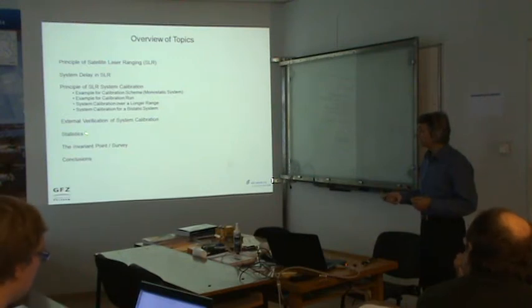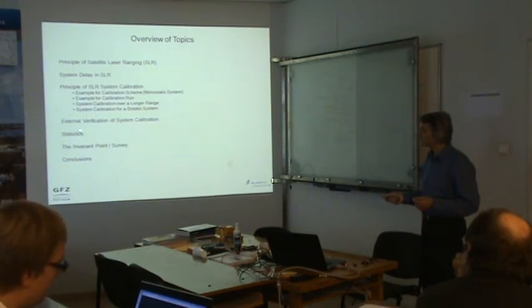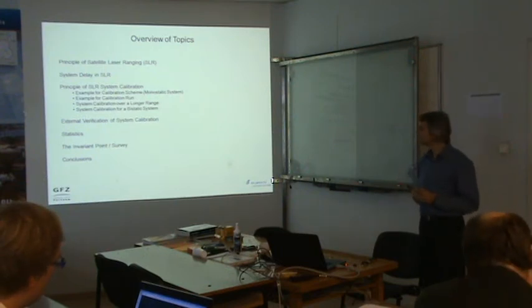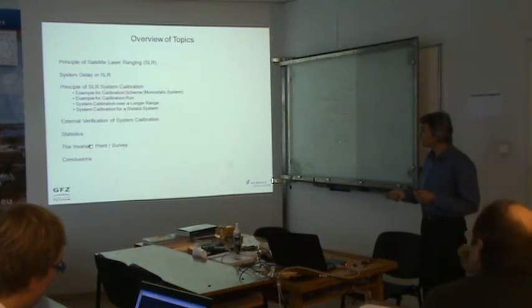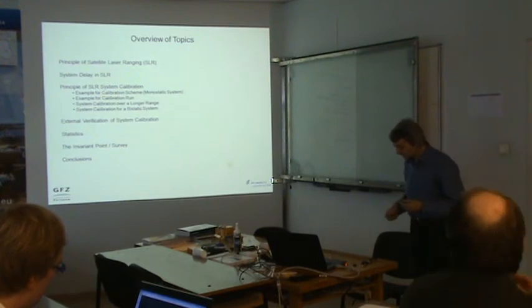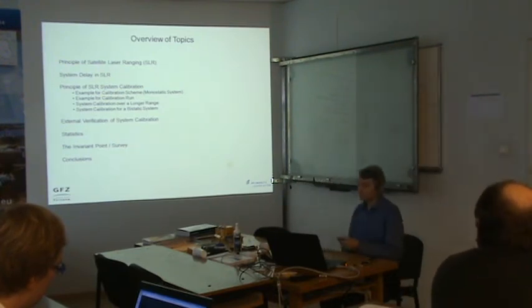We'll give some examples of target calibration statistics. Jorge Del Pino got the brilliant idea several years ago to record not only the mean value and the standard deviation, as is required, but also the higher moments like bias, skewness, kurtosis, and so on, which tell you a lot about the behavior of the system. And finally, I will turn to a thing which may be a little bit outside, but for the calibration you need in any case the invariant point of your system. How do you get it by a survey? And how do you perform a geodetic survey in a larger area? And finally, I will draw some conclusions about what we've heard. You will see where we make the break in between.